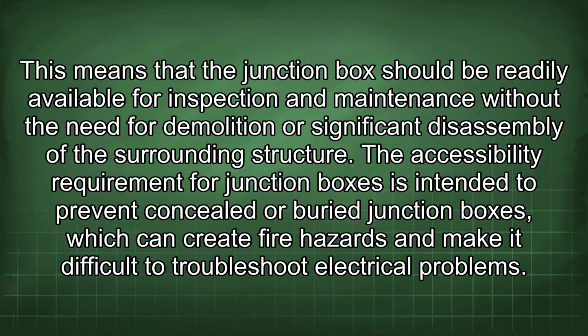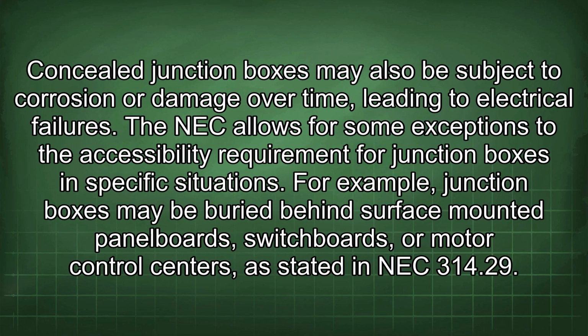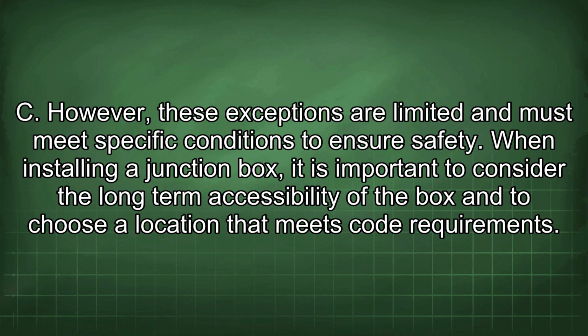The accessibility requirement for junction boxes is intended to prevent concealed or buried junction boxes, which can create fire hazards and make it difficult to troubleshoot electrical problems. Concealed junction boxes may also be subject to corrosion or damage over time, leading to electrical failures. The NEC allows for some exceptions to the accessibility requirement for junction boxes in specific situations. For example, junction boxes may be buried behind surface-mounted panel boards, switchboards, or motor control centers, as stated in NEC 314.29(C). However, these exceptions are limited and must meet specific conditions to ensure safety.